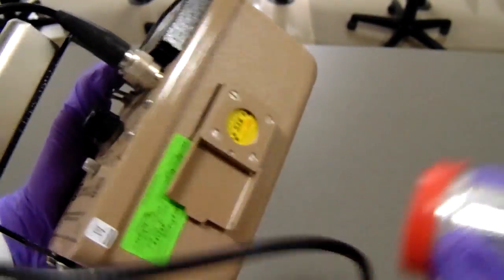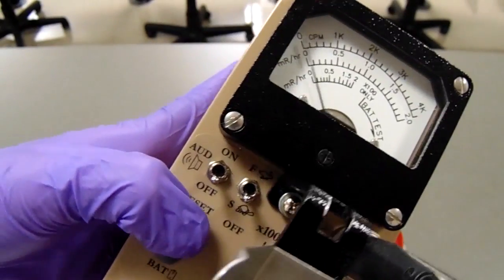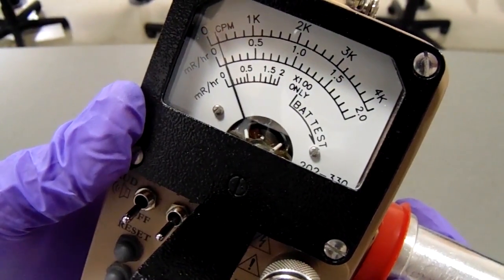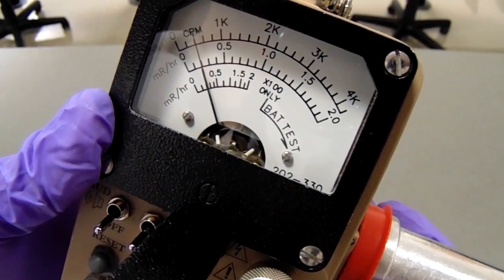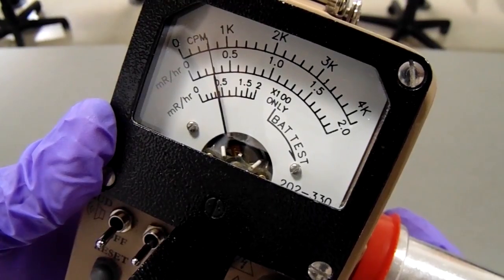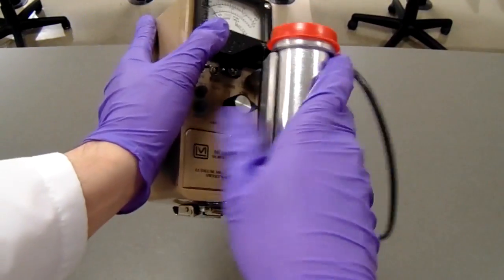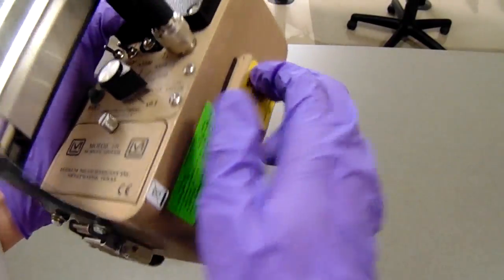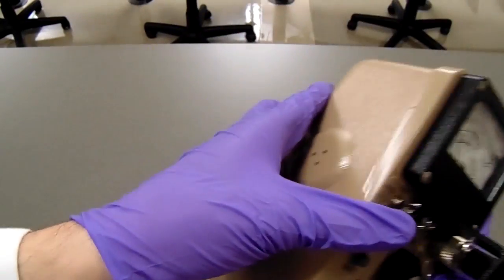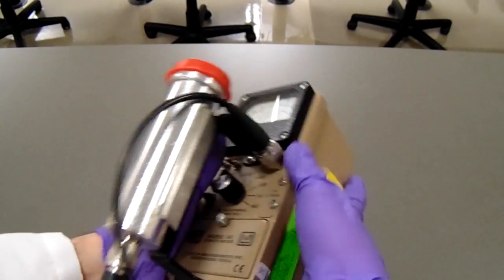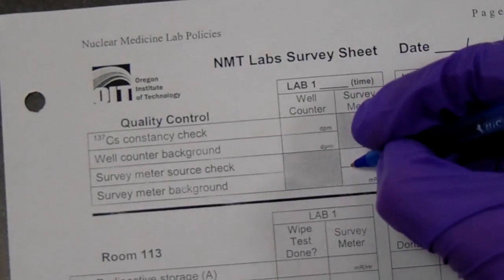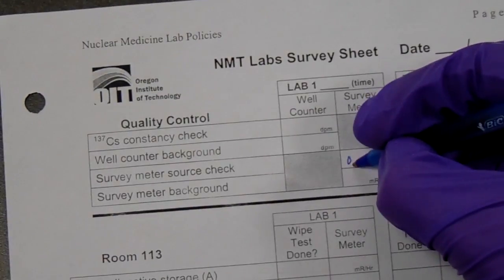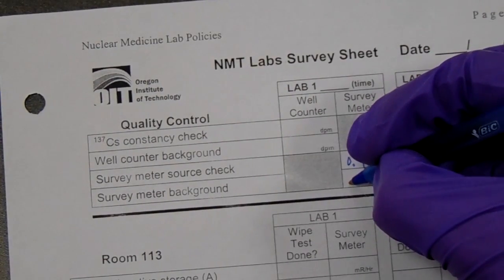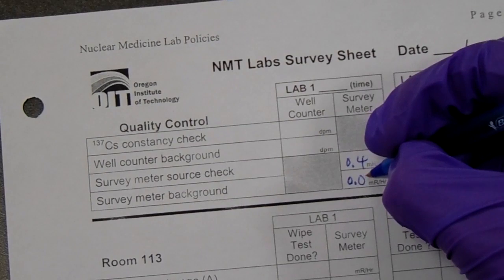Now we're going to check the cesium source and turn the knob to the ×1 multiplier, open the garage door, and place the probe right up against the cesium source and reset the meter. And the reading on this is probably going to be about a 0.4 or 0.3. Now you put the probe back and close the garage door and twist the knob back to off. Now your constancy is done on your GM meter, and you're gonna record your background and your source check on the survey meter, which is also a GM meter, on your wipe and survey lab sheet in the binder.